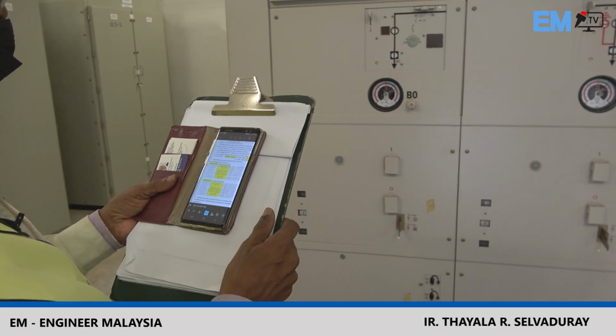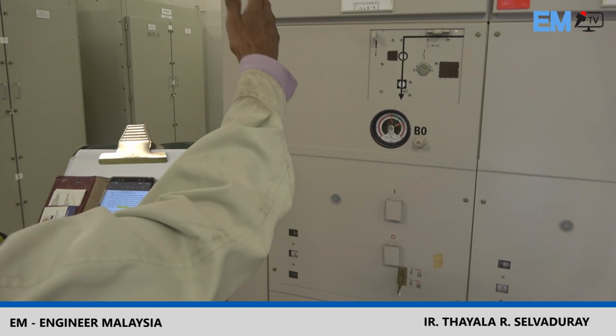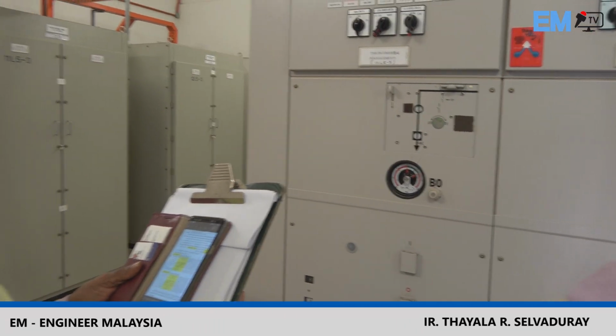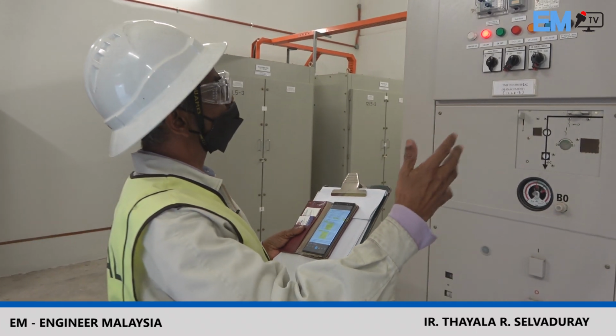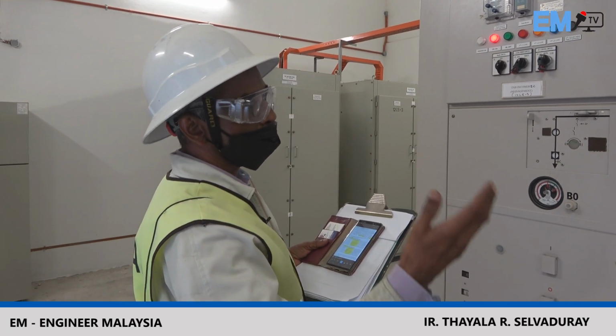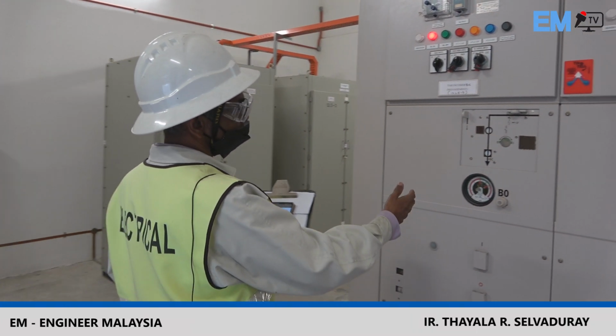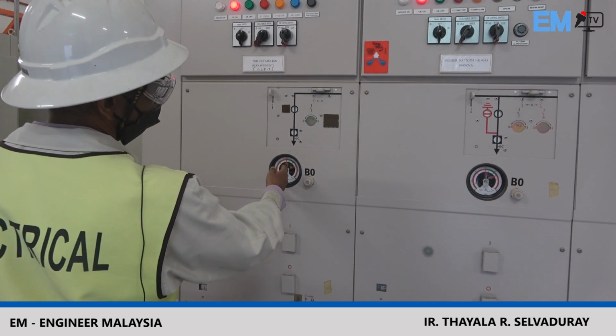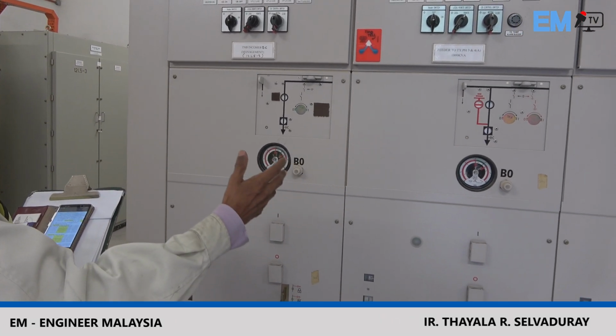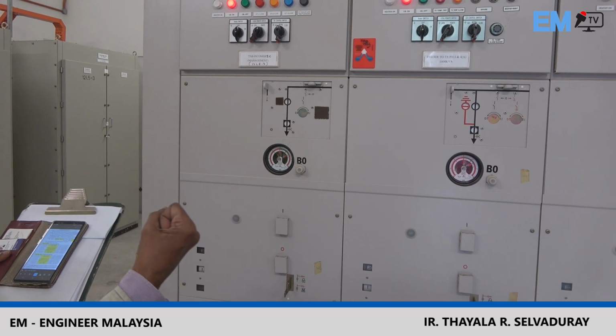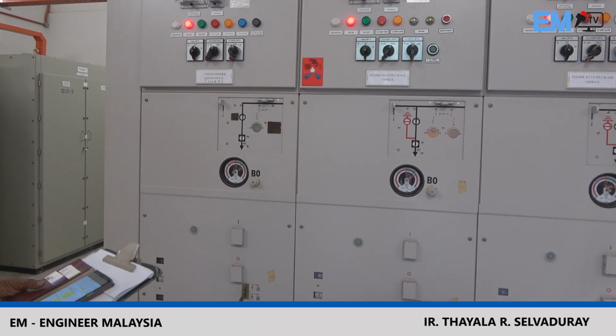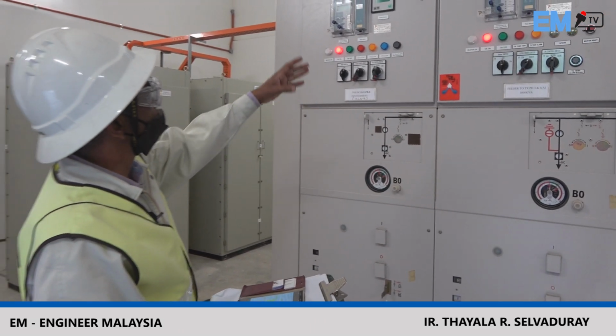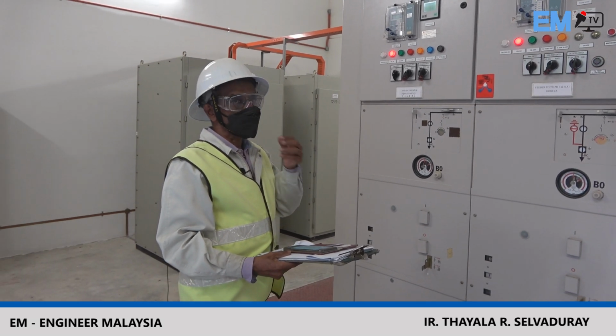Now I'm going to take the readings on the management supply and later on the tenant supply. So these two readings will tell me what sort of consumption is going. On top of that, I also have got to look at the gas here, called SF6, which are very important inert gases for quenching any internal arcs.